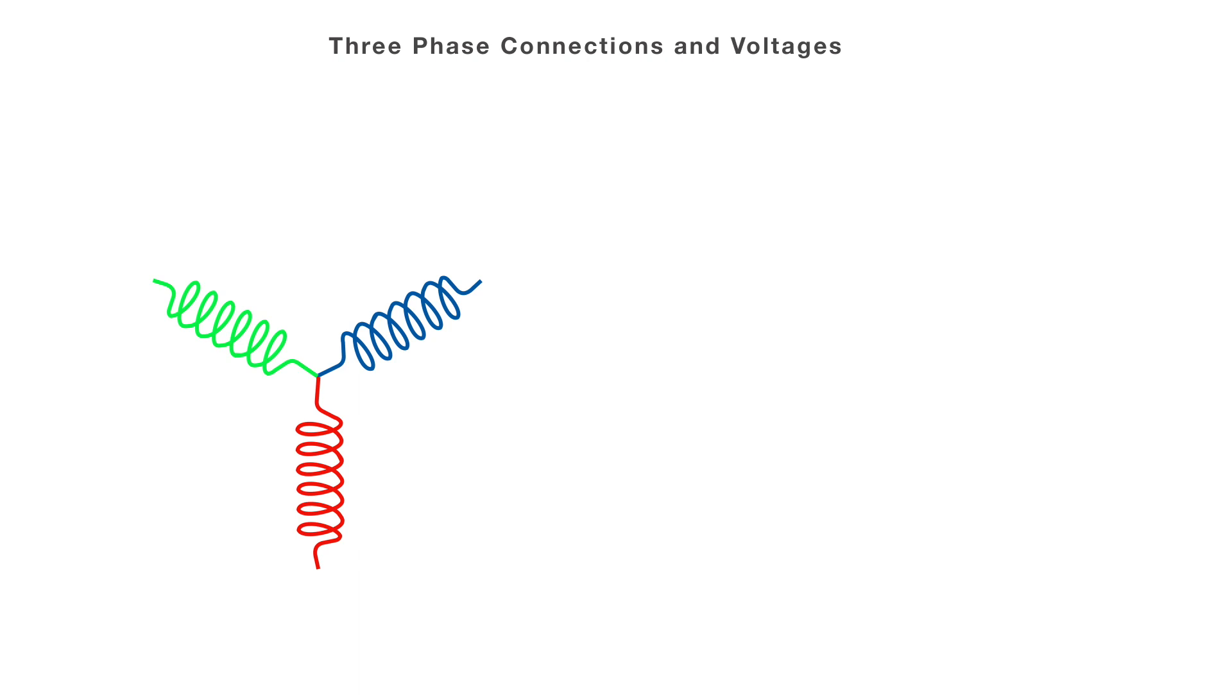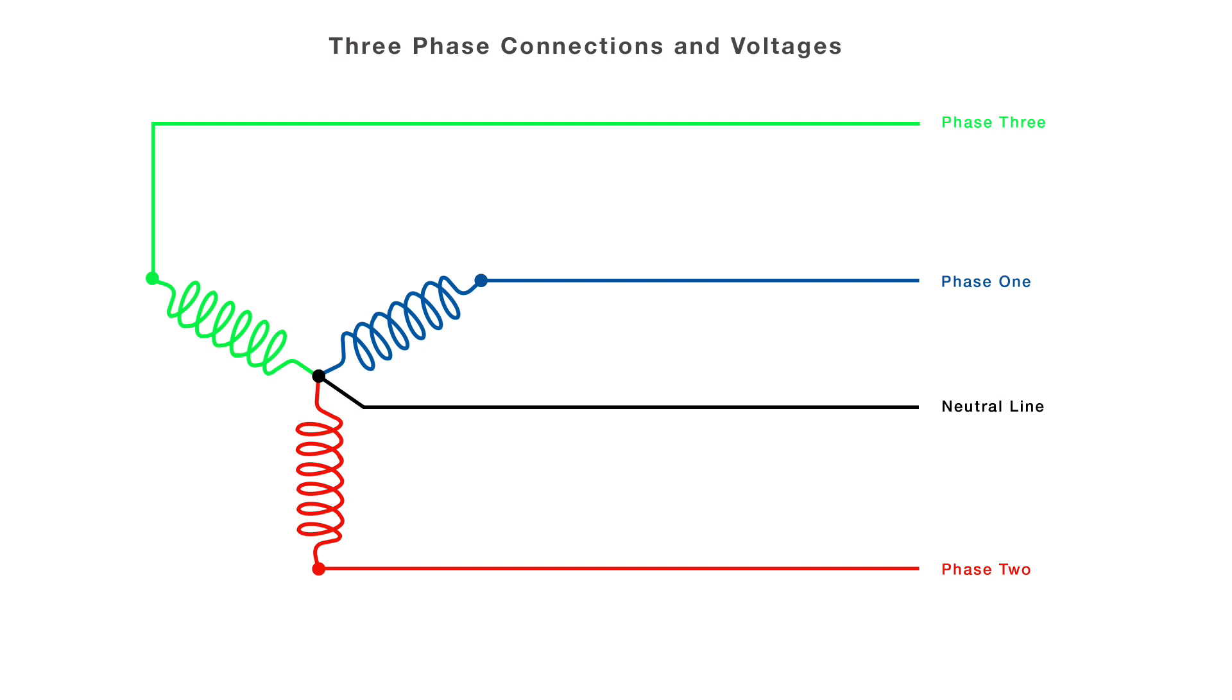In the most common star connection, phase one, phase two, and phase three are connected in a star format. The neutral line is connected to the center of the star arrangement. Another line is connected to phase one, then another to phase two, and then the third phase to phase three. In a series star connection, the voltage read between phase one and neutral is 277 volts.